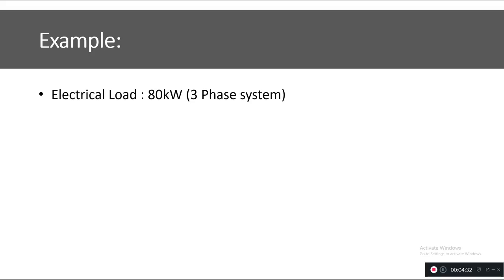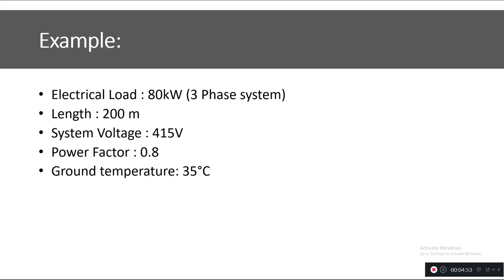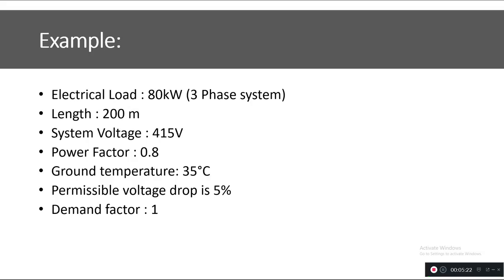We will consider an example with an electrical load of 80 kW on a three-phase system, a cable length of 200 meters, a system voltage of 415 V, and a power factor of 0.8. The ground temperature is 35°C, meaning we are laying the cable underground at a depth of 1 meter. The permissible voltage drop is 5%, the demand factor is 1, and the soil type is damp soil.